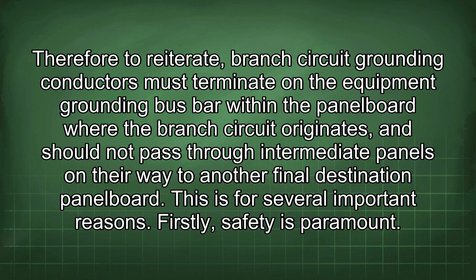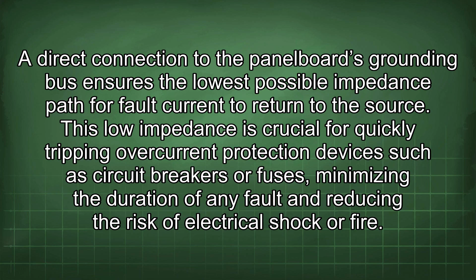This is for several important reasons. Firstly, safety is paramount. A direct connection to the panel board's grounding bus ensures the lowest possible impedance path for fault current to return to the source. This low impedance is crucial for quickly tripping overcurrent protection devices such as circuit breakers or fuses, minimizing the duration of any fault and reducing the risk of electrical shock or fire.